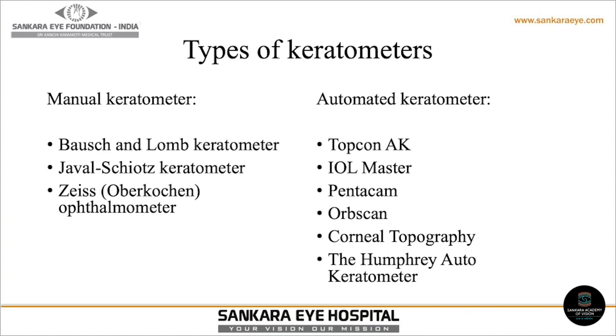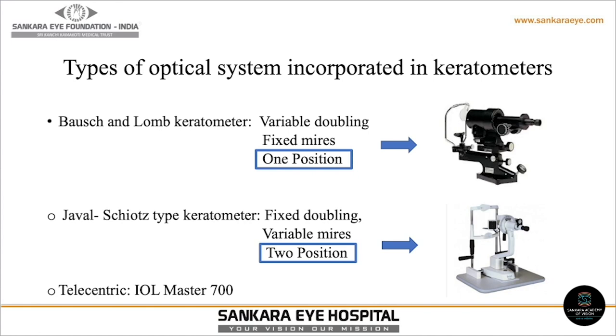The optical system incorporated in the Bausch and Lomb keratometer is a one-position keratometer, where double images are produced side by side as well as at 90 degrees from each other. The principal meridians are assumed to be at right angles to each other, with a fixed object size, variable image size, and variable doubling. This is exactly the opposite in the Javal-Schiotz type, which is a two-position keratometer requiring rotation about the axis to measure each of the principal meridians.